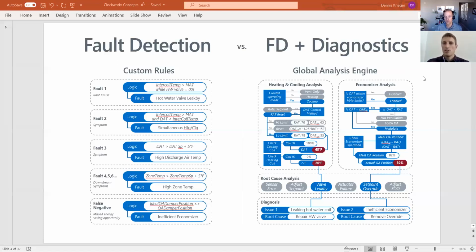That analysis engine is not a kind of siloed rule set, it's a connected set of algorithms. So when we look at an air handling unit, we account for the fact that the preheat coil is contributing heat to an airstream that's being cooled by the cooling coil. When we check those things, we do it holistically, so you get two root causes instead of many symptoms, because that analysis is truly connected.